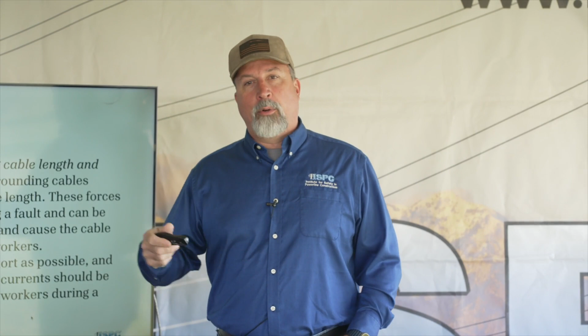This is a parallel 2-aught phase to ground, three times. So phase to ground, phase to ground, phase to ground. We just talked about how shorting phase to phase to phase, then one conductor to ground, will clear a fault a little quicker. Let's take a look at what this is going to look like when this fault happens.